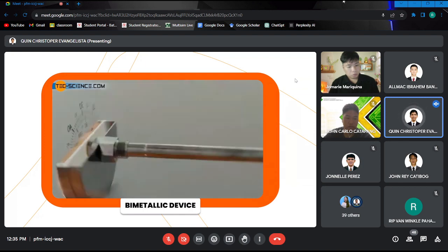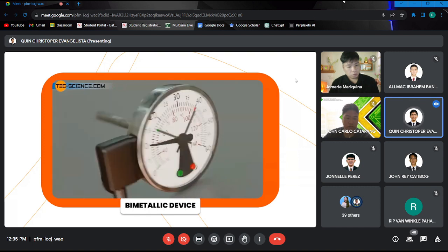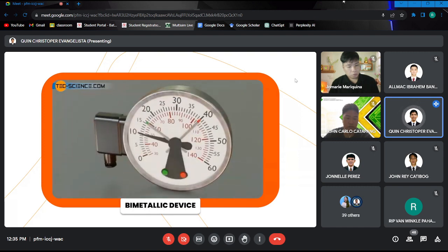Such bimetal thermometers can also be equipped with switch contacts which close an electrical circuit when a certain temperature is exceeded or undershot. An electrical signal is triggered accordingly. Switch contacts can thus perform control tasks, for example as a thermostat for underfloor heating systems, which switches off the heating pump for safety reasons when temperatures are too high and switches it on again when the temperature falls below a certain level.